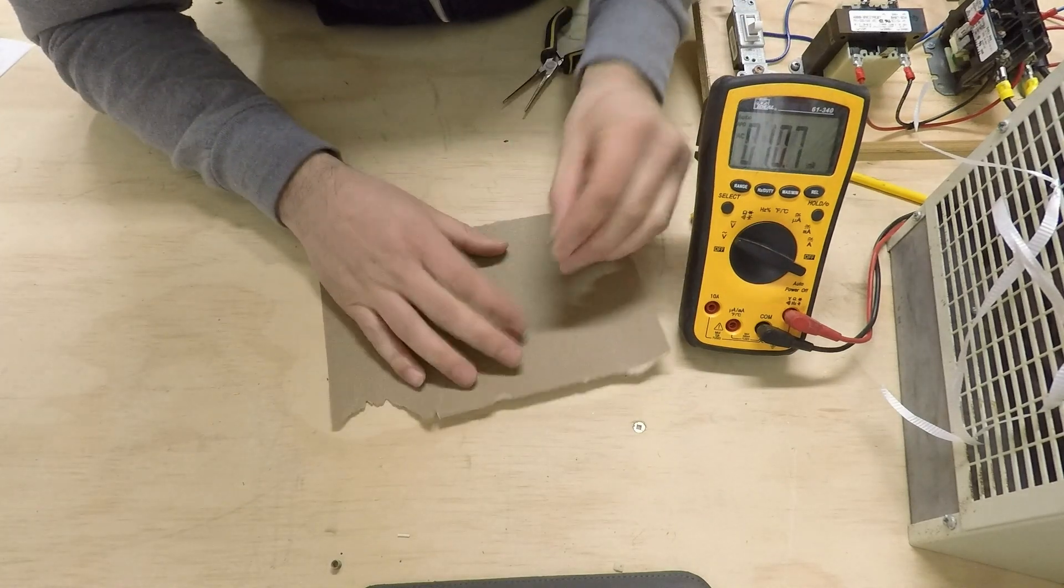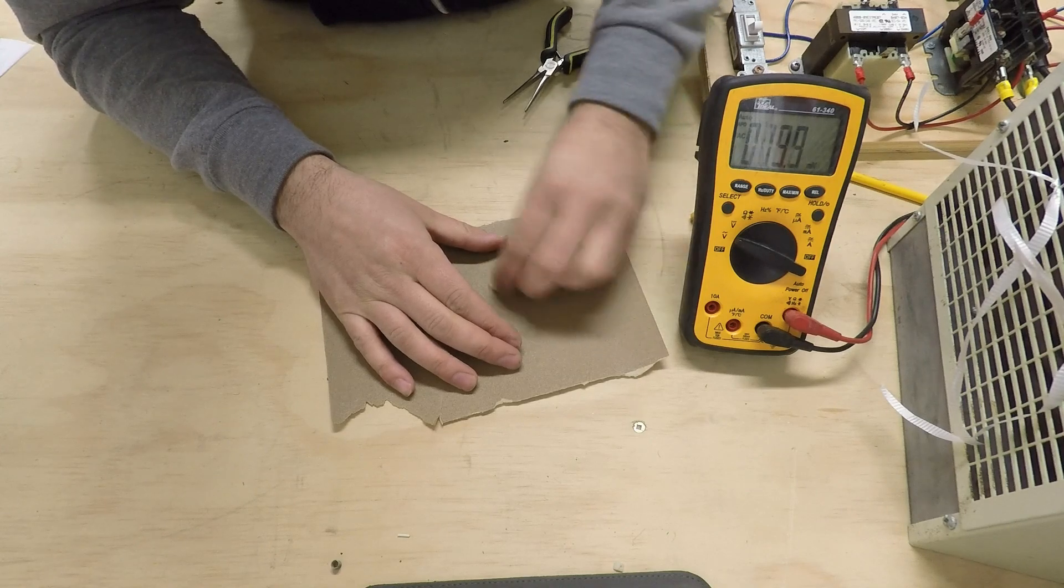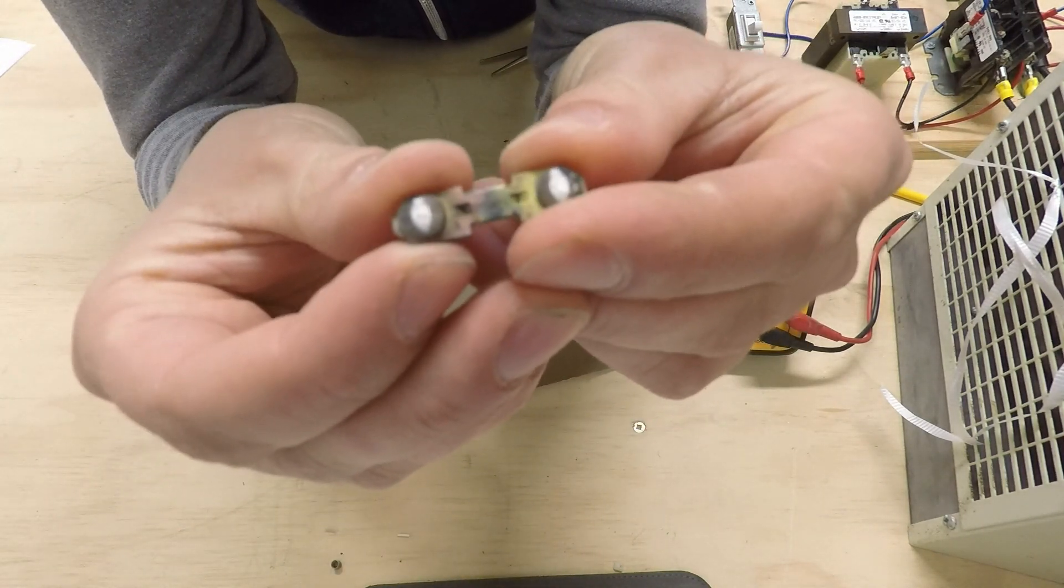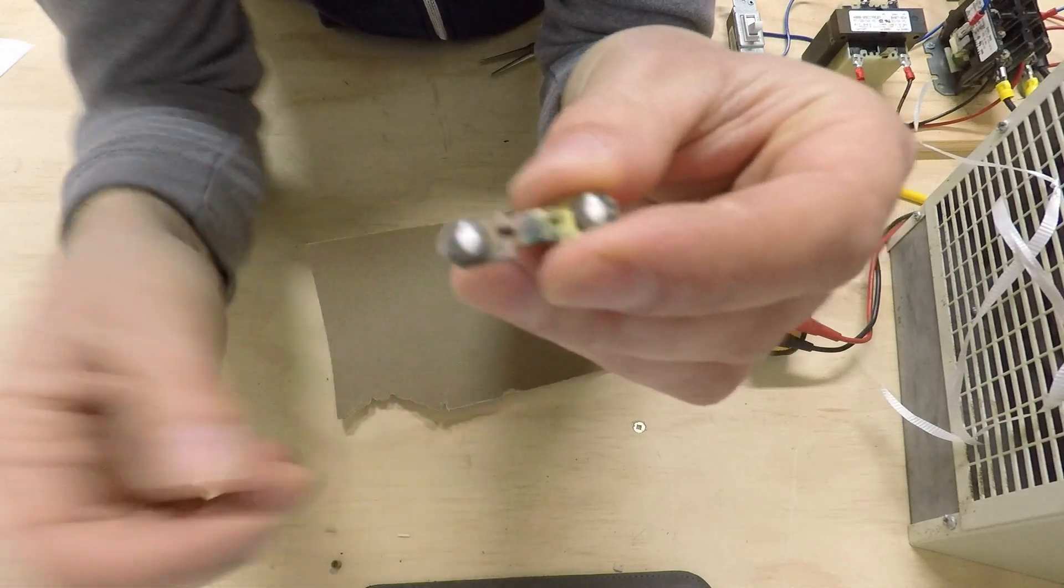So you take some sandpaper and just rub that contact on there around a little bit to take off that layer, take off the layer of carbon. And then when you look at it again, you can see the bright metal surfaces now. So that contact surface is good to go.